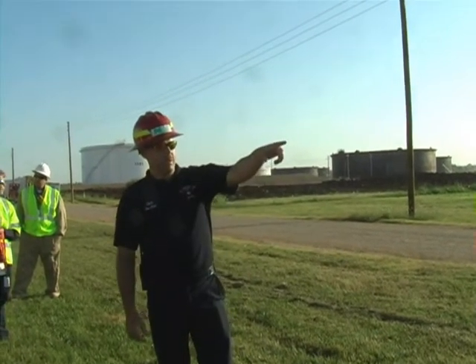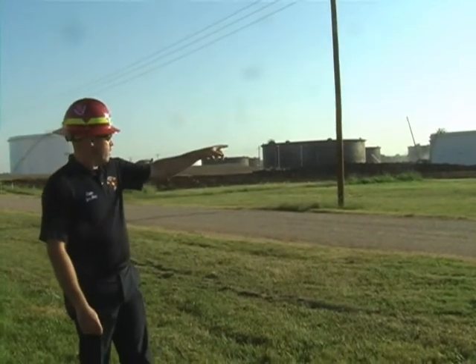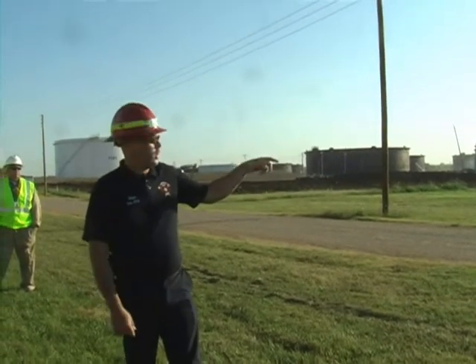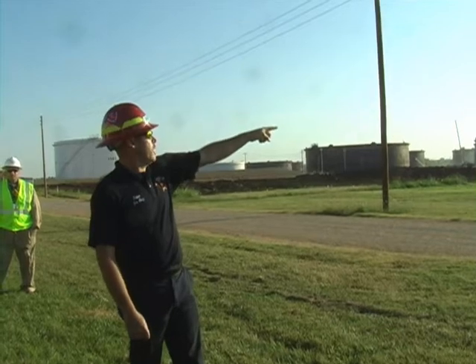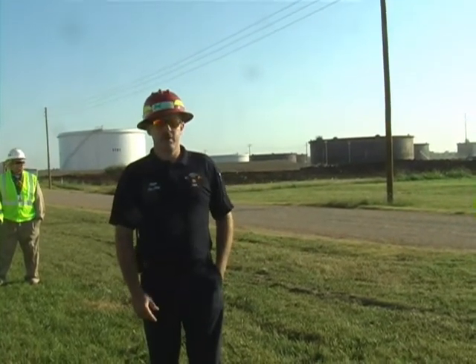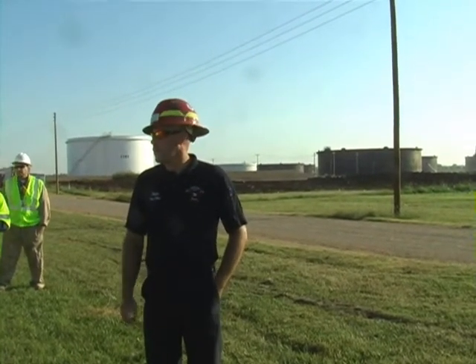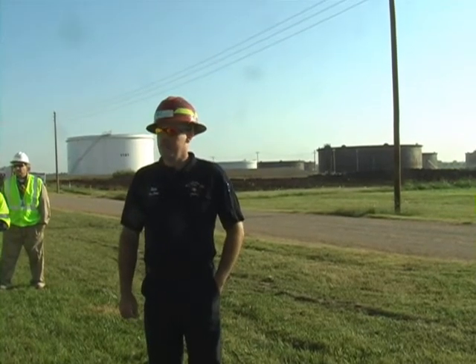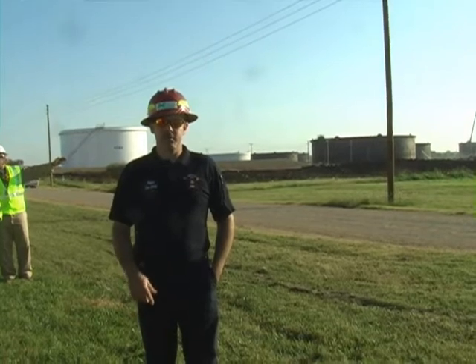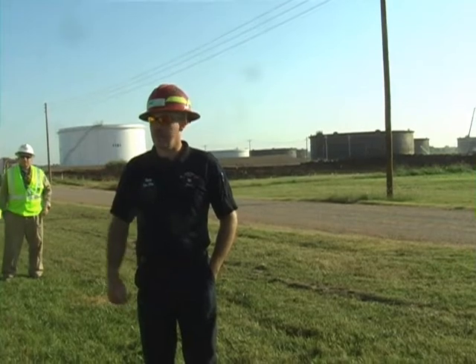If you look back at this pond over here, that's a 6,000 gallon per minute pump. It's feeding the first pump here to a monitor. We'll be proportioning foam at that pump. The second pump is at the pond back straight to the east back there, and it's actually a 9,000 gallon per minute pump. It's feeding another monitor. The 2 monitors combined will get us right at 12,000 gallons a minute. We'll demonstrate with a little bit of old foam first. Everything else we use today is red food coloring just to tint the water so we can actually see that we're proportioning.